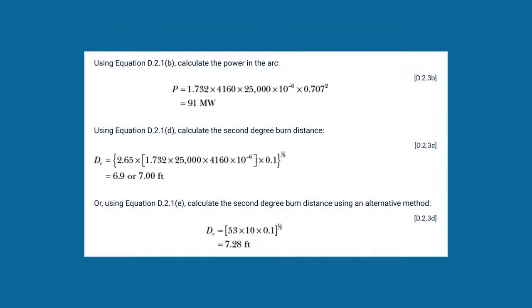Next, you calculate the power in the arc, and then the second degree burn distance. Then I'll show you a different alternative method that's much easier. The one we're doing right now is pretty exact, while the other is more of a conservative calculation. To determine the power, you take 1.732 for three-phase, times 4160 volts, times 25,000 for the short circuit current, multiplied by 10 to the minus 6th power, and then multiplied by 0.707 squared, which gives you 91. That's your power.